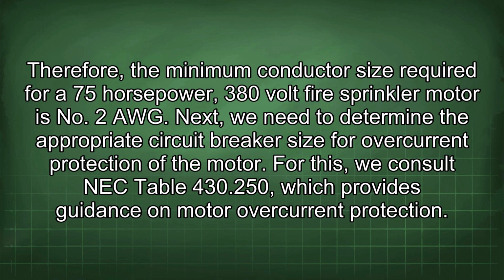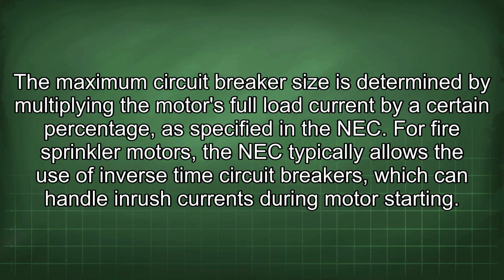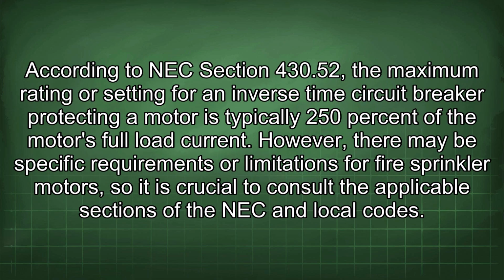For this, we consult NEC Table 430.250, which provides guidance on motor overcurrent protection. The maximum circuit breaker size is determined by multiplying the motor's full load current by a certain percentage as specified in the NEC. For fire sprinkler motors, the NEC typically allows the use of inverse time circuit breakers which can handle inrush currents during motor starting.